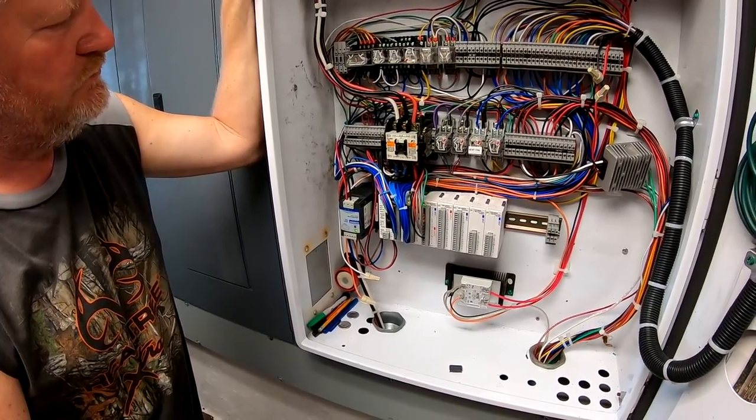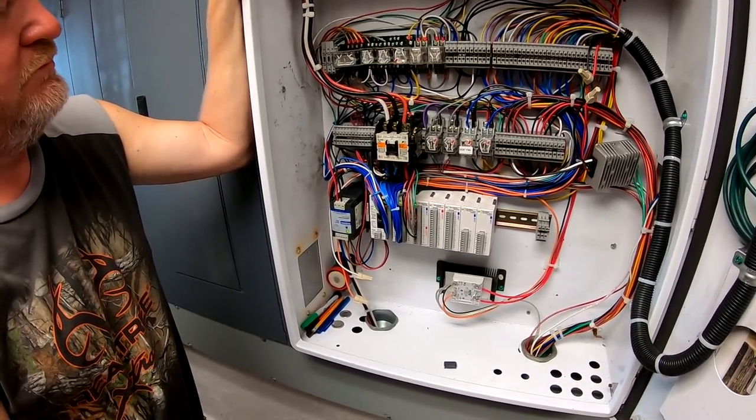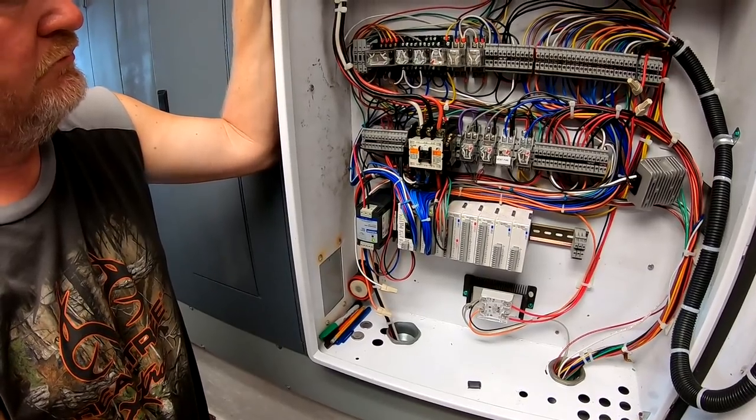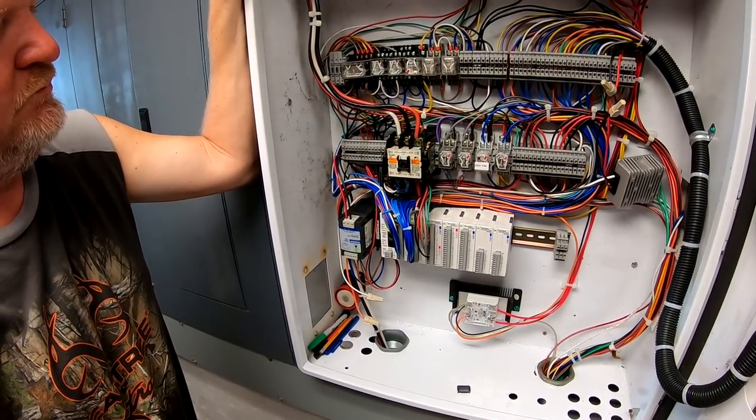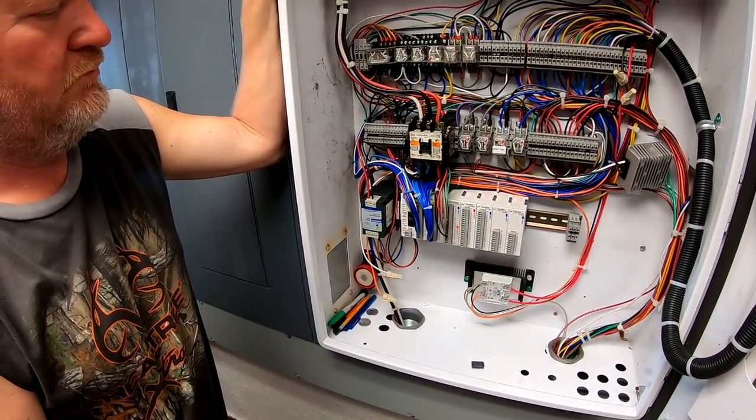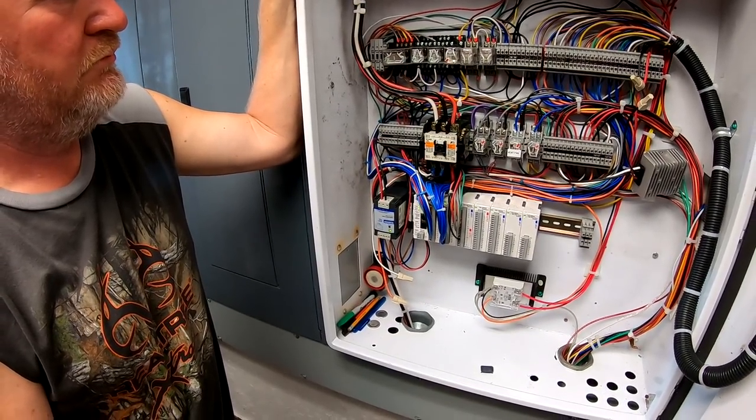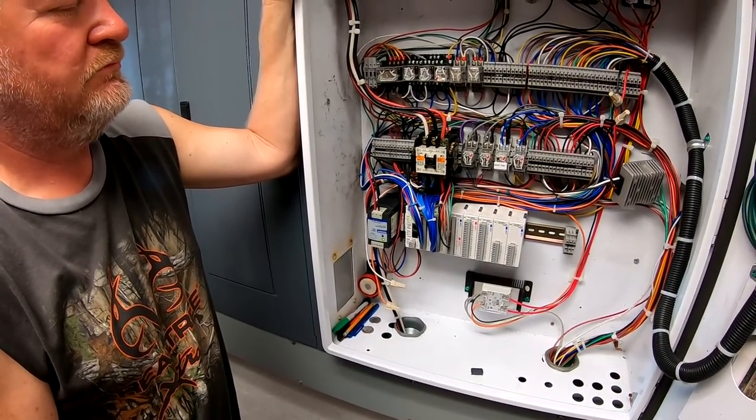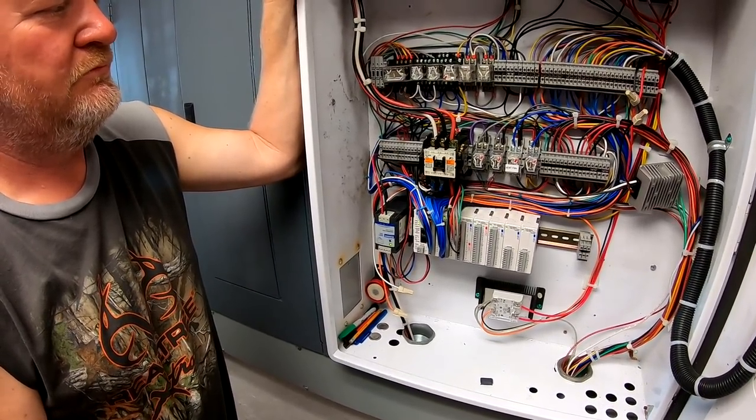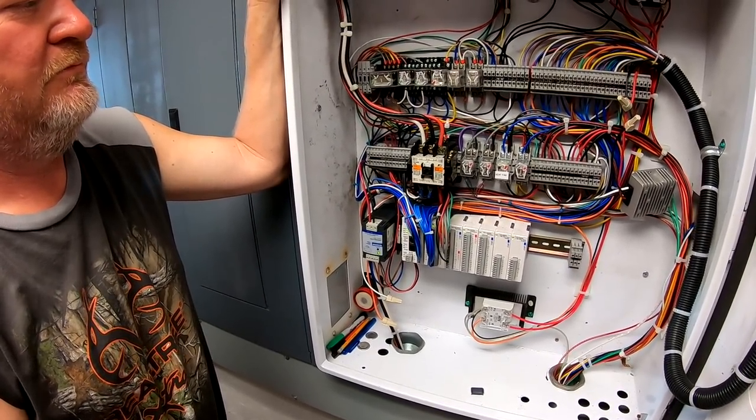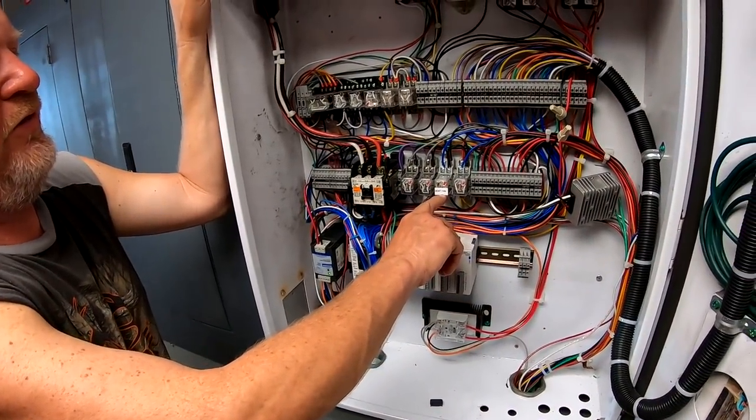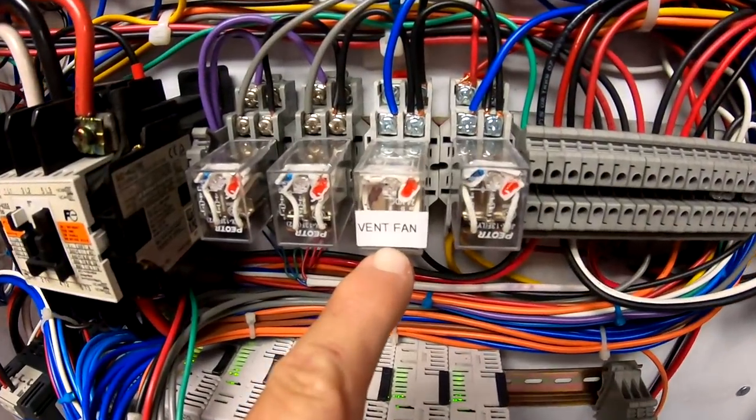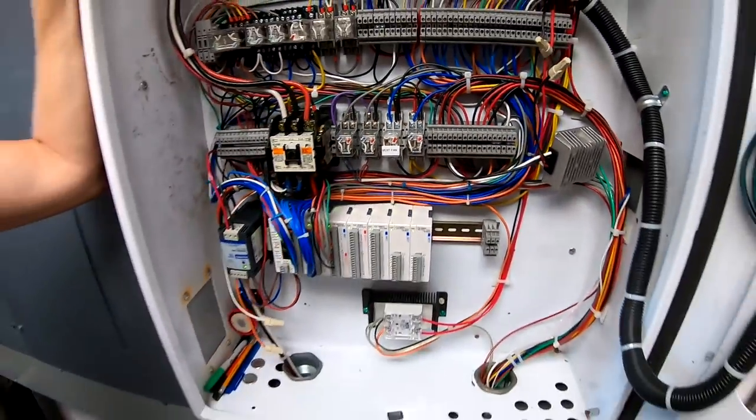And this big piece right here? Yeah, that's our switch that lets all the power take from the generator to take over the power off the batteries. So what that does is that's the main power coming in from the generator. So when we want to shut the generator off, that opens up and allows the generator to cool down before it shuts off the motor. And it also allows it to warm up without a load before it starts loading down.